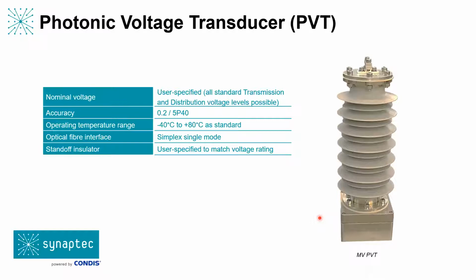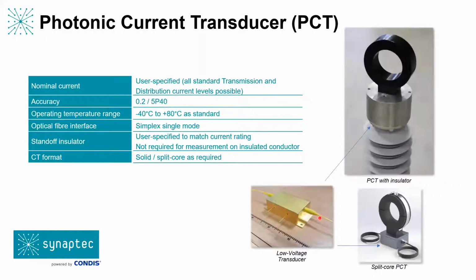So that will make a primary measurement of voltage, for example. If we wanted to make a secondary measurement of voltage, it would be the same technique, but it would be a device spec'd for attachment to the secondary side, for example, of an existing VT that was in situ. Likewise, for current measurement, again, it's one fiber in, one fiber out that leads to the next sensor, because all the sensors can be connected together in series.